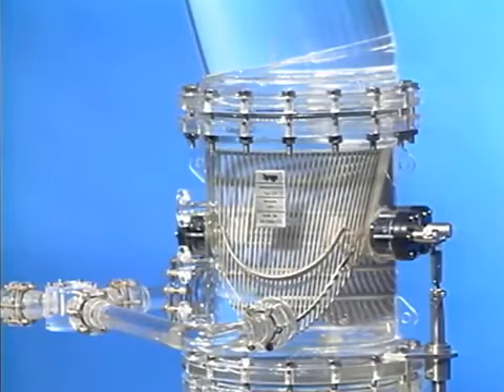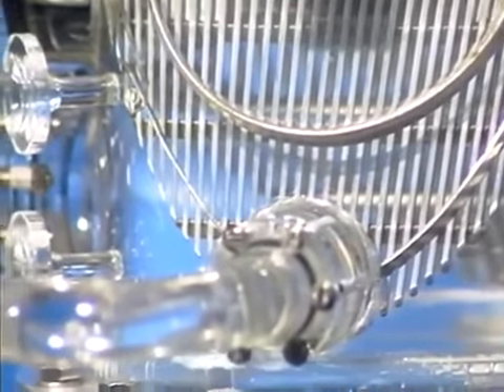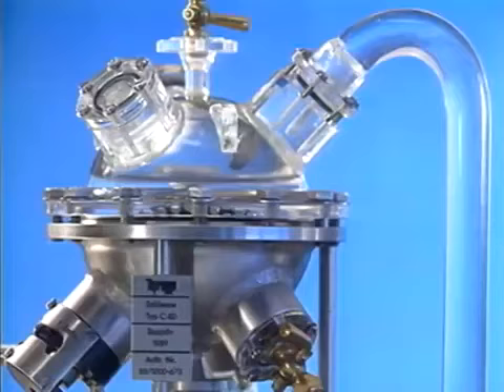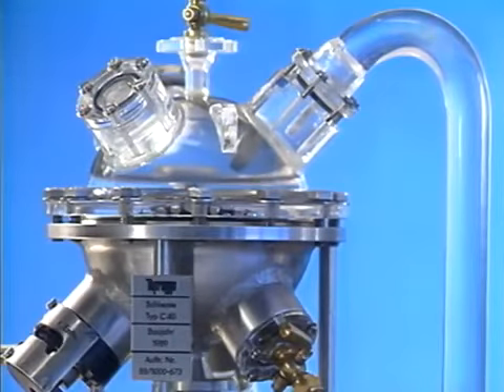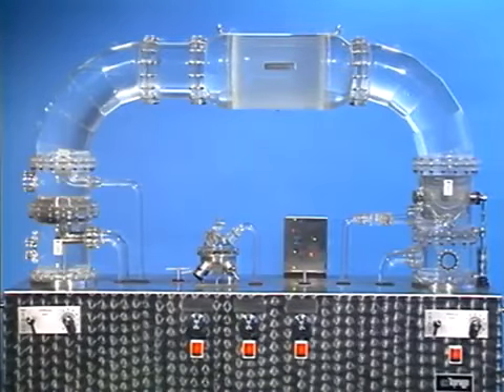At the condenser outlet, the sponge rubber balls are removed from the cooling water system by the strainer screens. And returned to the condenser inlet by the recirculation unit. A closed cleaning circuit. The Taprogge system cleans the condenser continuously online during actual operation. A simple and effective solution.